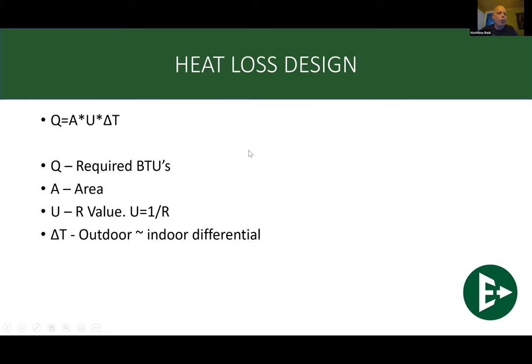Q is the required BTUs. Why is it Q? There is a scientific mathematical term that goes with that, but whatever. It just means BTUs. A, super easy, that's your area. U is your R value; in order to find U, it's 1 divided by R. So if you have R20 insulation, 1 divided by 20 gives you your U value. And of course, you've got your delta T, which is your outdoor temperature versus your indoor, and that is the differential you're looking for. So if you're designing around here in Barrie, where we design to minus 10, and we want the indoor temperature to be 70, we have an 80 degree delta T.